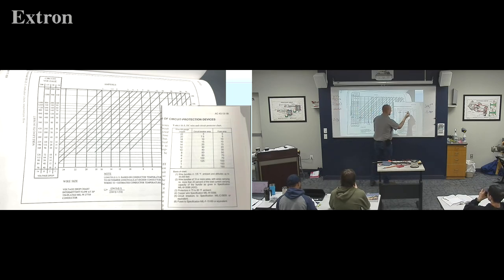Now, I could put a 5 amp breaker in. That'd protect my wire, but 5 amps ain't gonna cut it. Because 7.5 was the maximum size breaker, if I actually installed the wire that the chart said, I'm not gonna be able to run my component because my circuit breaker is gonna trip, right?